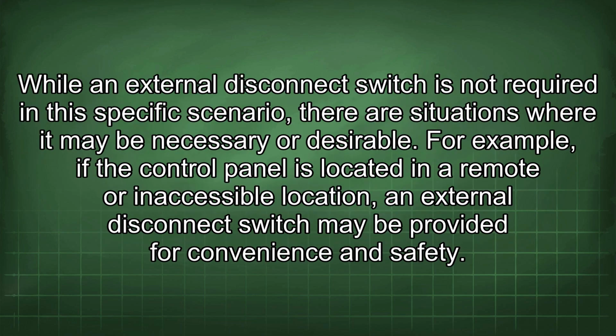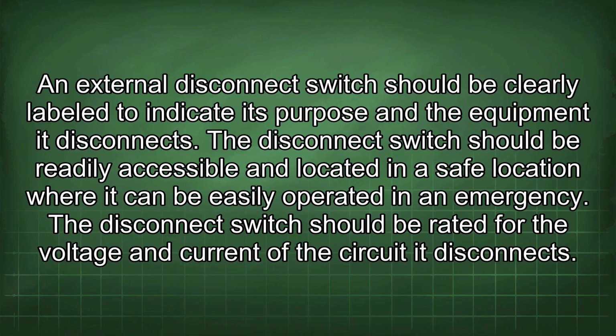While an external disconnect switch is not required in this specific scenario, there are situations where it may be necessary or desirable. For example, if the control panel is located in a remote or inaccessible location, an external disconnect switch may be provided for convenience and safety. An external disconnect switch should be clearly labeled to indicate its purpose and the equipment it disconnects. The disconnect switch should be readily accessible and located in a safe location where it can be easily operated in an emergency. The disconnect switch should be rated for the voltage and current of the circuit it disconnects.